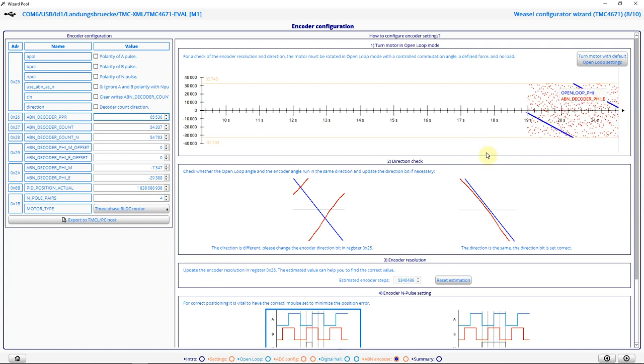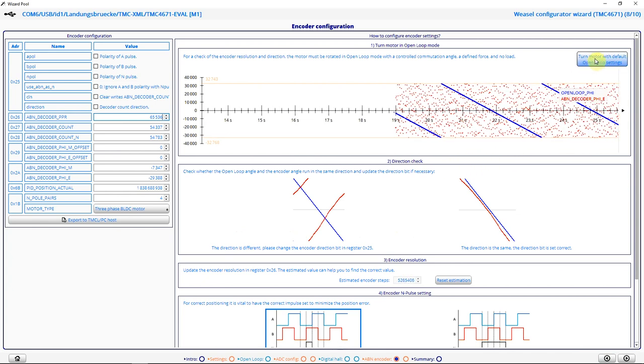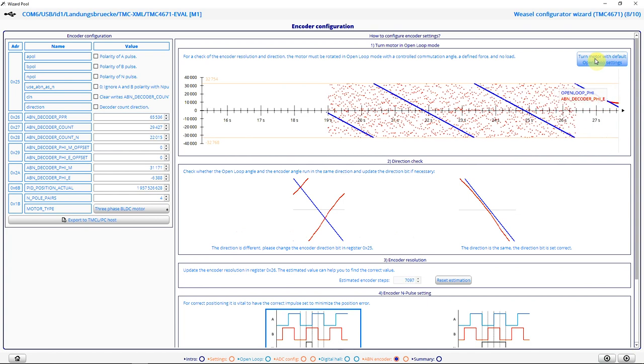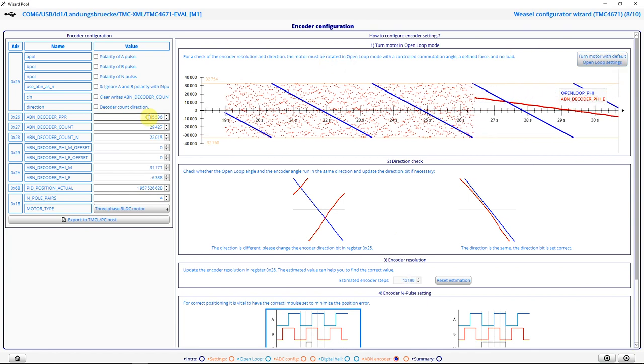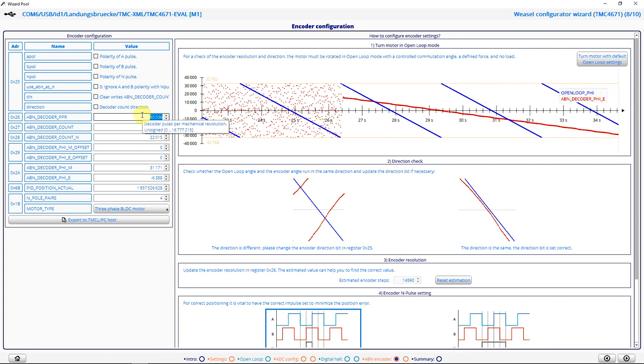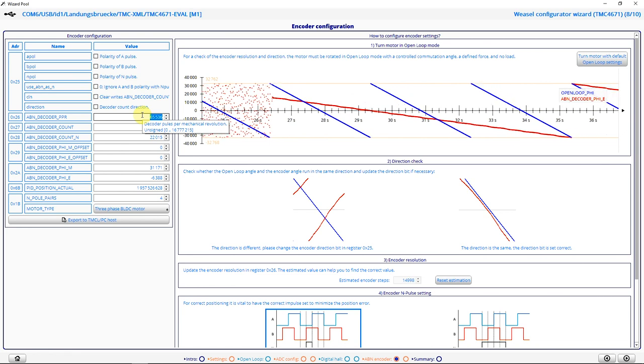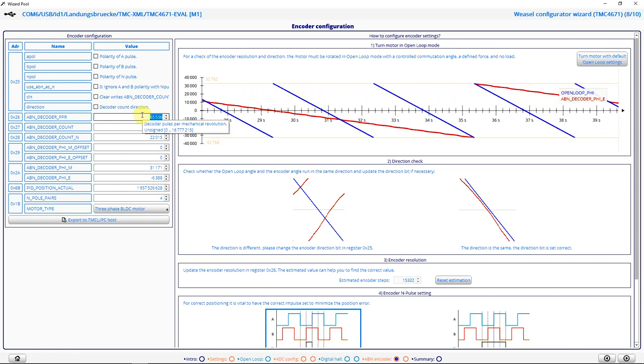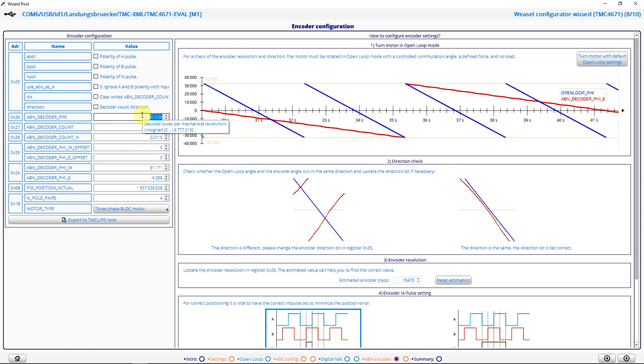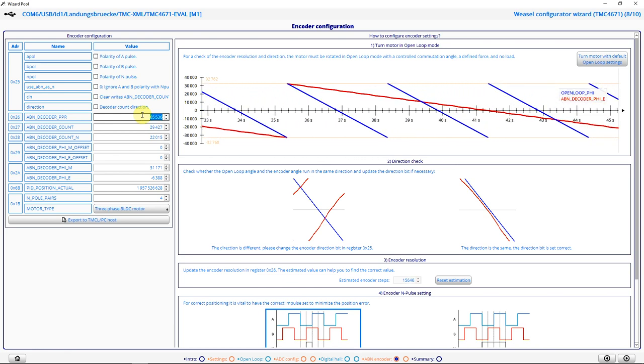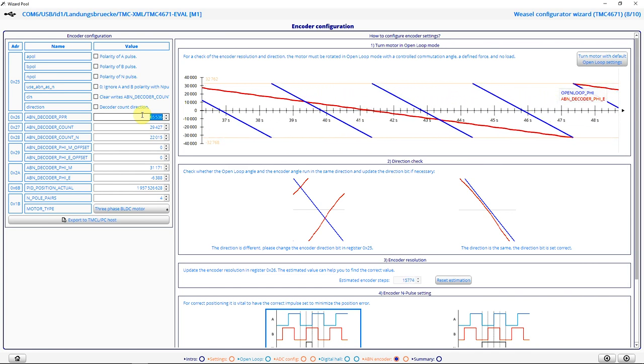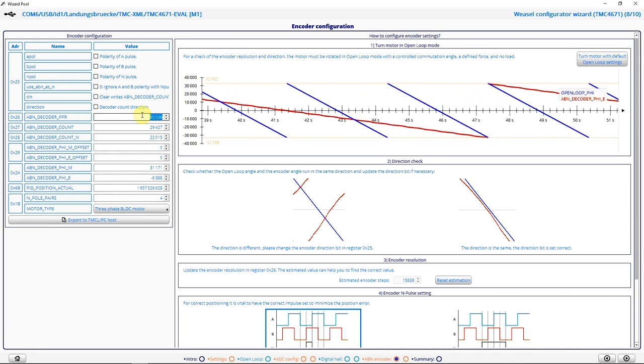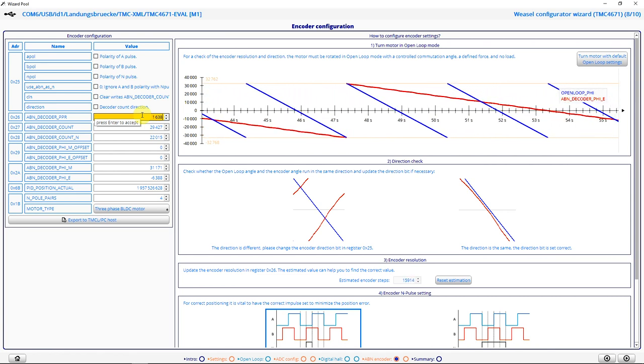Now I want to configure my ABN encoder. So I switch back to open loop mode by clicking this button. Now I have to put in my encoder PPR. That's the number of positions per revolution. My encoder has 4096 lines per revolution. And my PPR are four times that number. So I have to put in 16384.